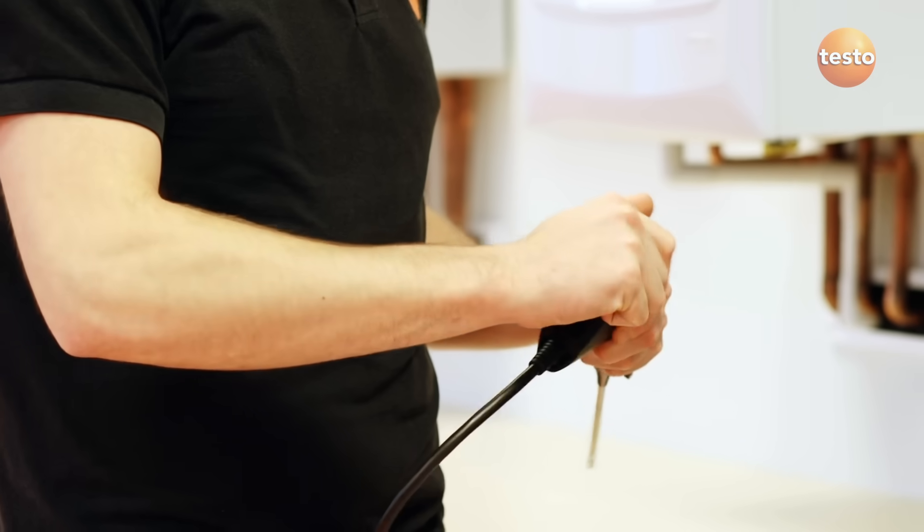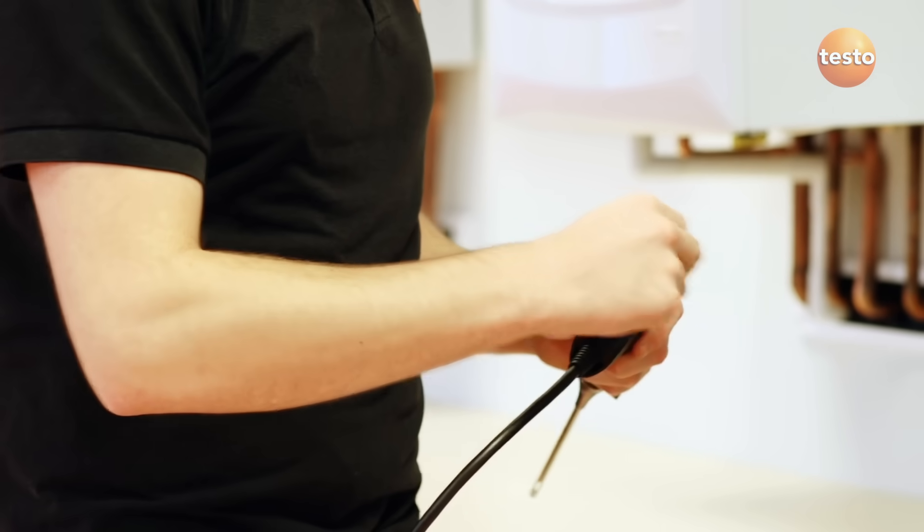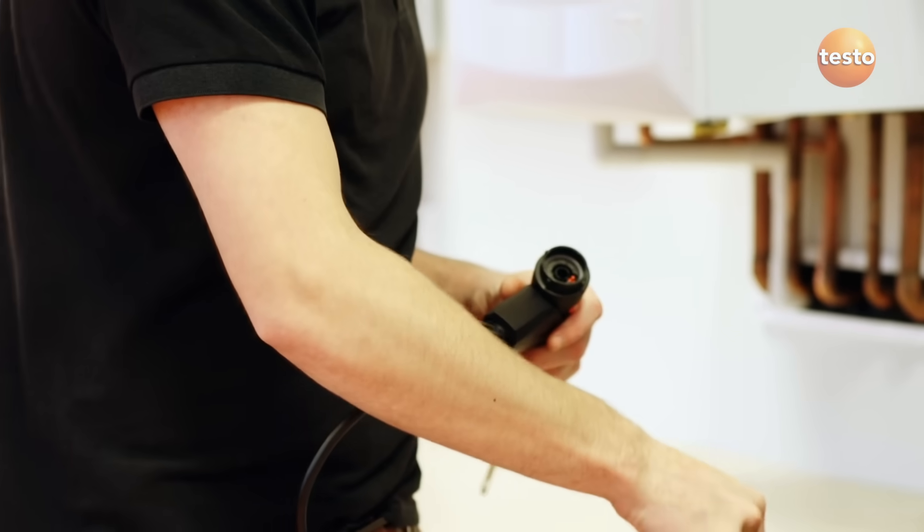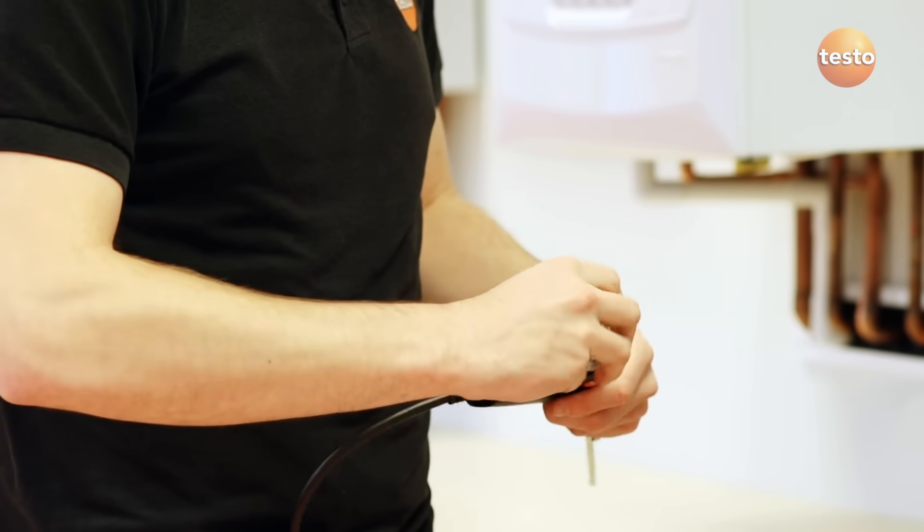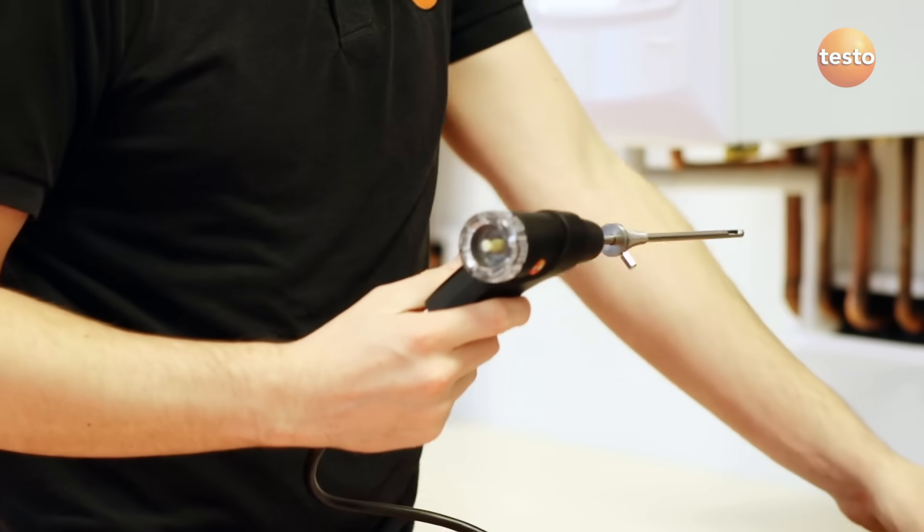Regularly check the filter on the probe handle, which is really easy to do on the 310. If the filter is dirty, then throw it away for a new one. If it's wet but clean, you can fit a dry one and keep the old one to dry out.